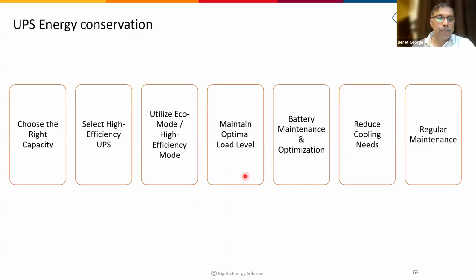So choose the right capacity, or you can also get modular UPSs so that you will have maximum efficiency operation in the UPS. And also purchase a high efficiency UPS and use eco mode or high efficiency mode. Then maintain optimal load level. Then battery maintenance, especially if it is a lead acid battery, maintaining properly, refilling the acid, etc. Then also see what temperature we keep in the UPS rooms. In some cases they keep it at 18 degrees Celsius. UPS is actually chilling. But we have to understand that we need not chill the UPS, we need only temperature maintenance. You can keep even 25, 27 degrees Celsius in the UPS room.